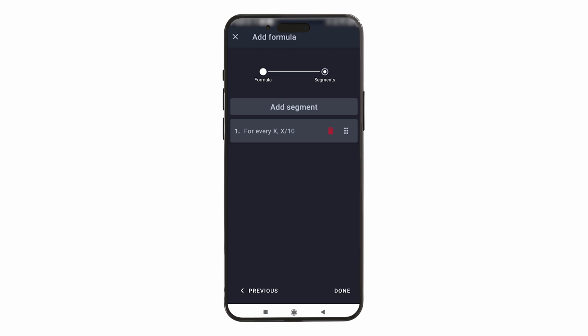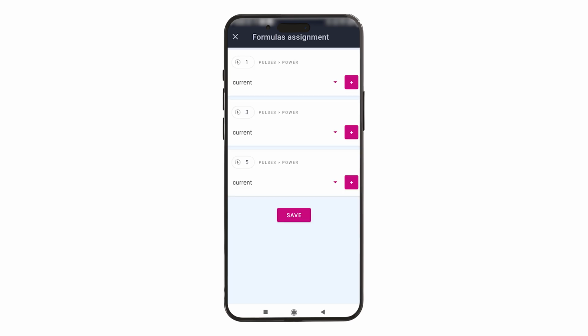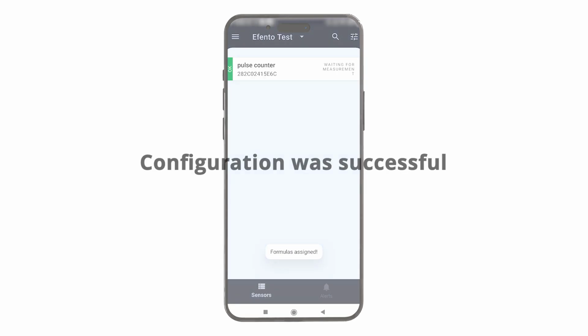In this way, you can add up to 6 segments for each formula. If more than one logical condition is met, the segment higher on the list will be selected for the final calculation of the values measured by the sensor. A measurement that does not meet any of the segment conditions will result in a channel error. Once the formulas for the channels have been configured, save the changes. Congratulations! The device has been successfully configured and added to the Efento Cloud organization. The first measurements will be displayed on the platform during the next communication between the sensor and the server.